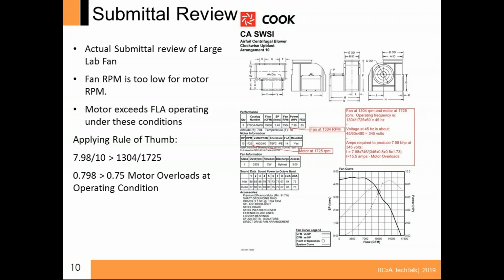Well, the problem is that at that reduced speed, about 45 hertz because it was spinning so slow, the voltage would drop so far down that the motor would overload. We caught this before we'd ordered it, and those fans end up becoming belt driven. It's kind of a shame. He should have put in a 1150 RPM motor and then oversped it above 60 hertz, which is not uncommon. And we probably could have got away with it the way it was. The system was oversized to start with, as we know happens all the time. We could have gotten away with a much better setup, but this is the way it went.